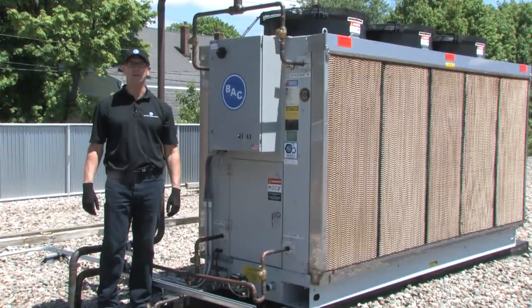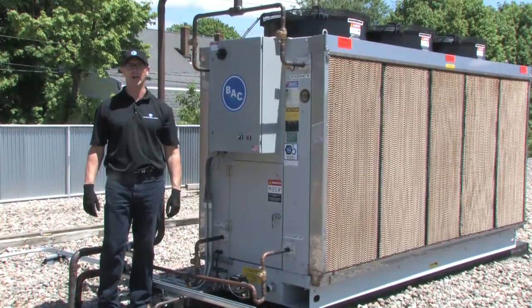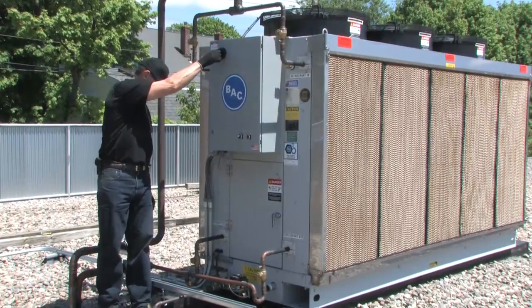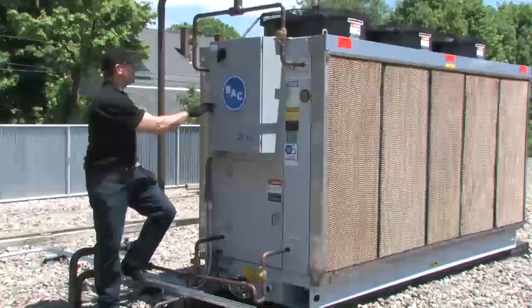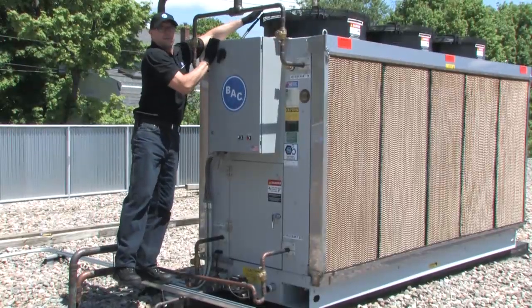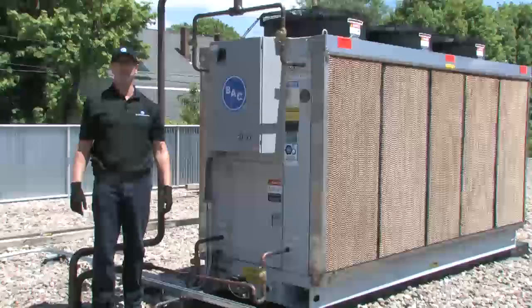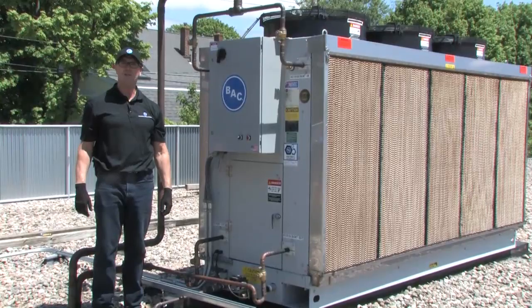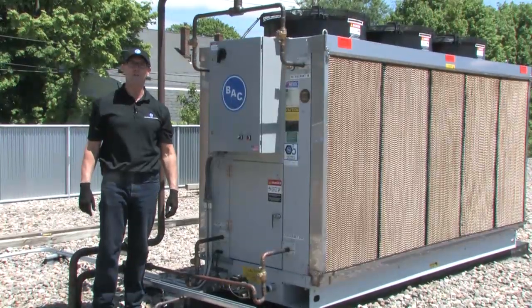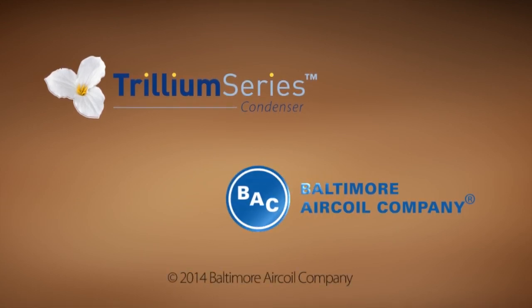Now that you've completed cleaning the Trillium series condenser, it's time to put everything back into operation. Turn the disconnect switch, hit the fan reset, make sure the fans are operating, and make sure the refrigeration system is on. That's how easy it was to clean the Trillium series condenser. Thanks for tuning in. This is Paul Noreen from Baltimore Aircoil Company.